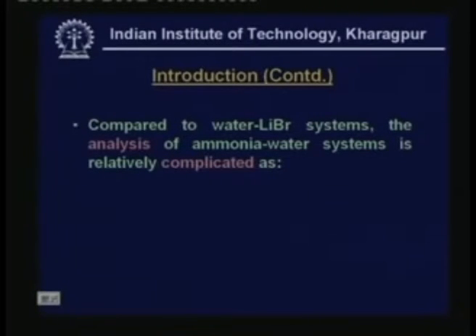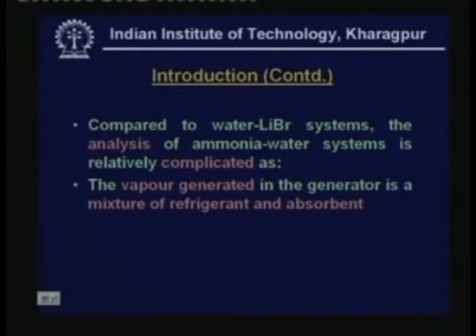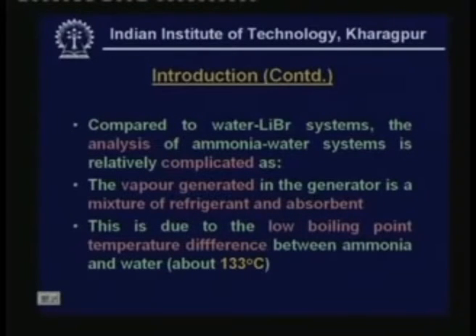However, compared to water lithium bromide systems, the analysis of ammonia water systems is relatively complicated. The complication comes because the vapor generated in the generator is a mixture of refrigerant and absorbent. The reason for this is the low boiling point temperature difference between ammonia and water, which is about 133°C. In water lithium bromide systems, the boiling point temperature difference between absorbent and refrigerant is very high, so in the generator the amount of absorbent is practically negligible — the generator exit produces pure water vapor, so you have pure refrigerant circulating in the refrigerant circuit.